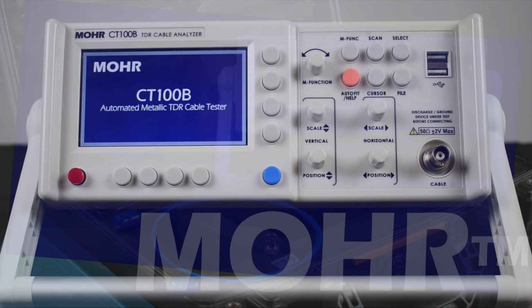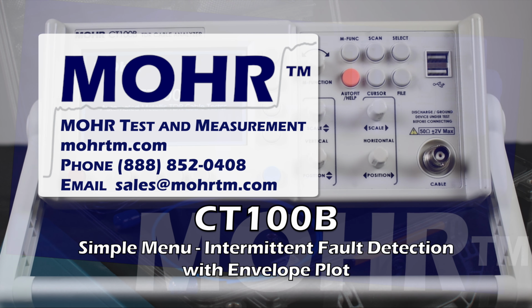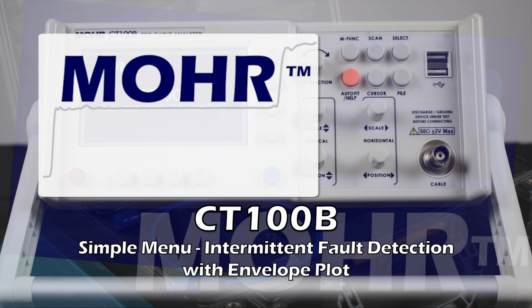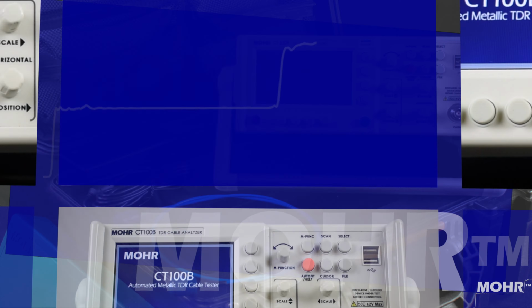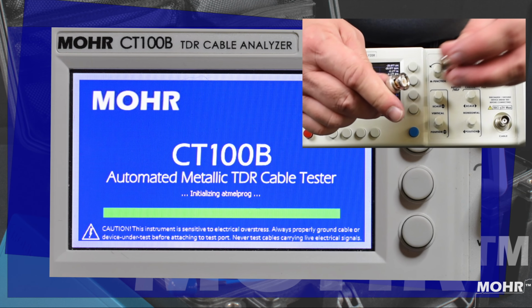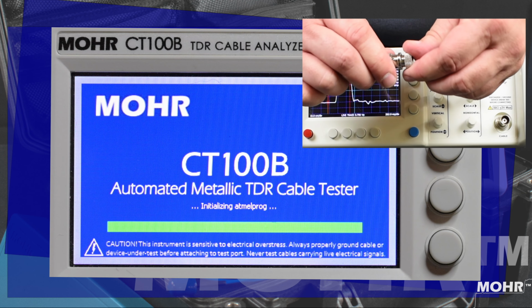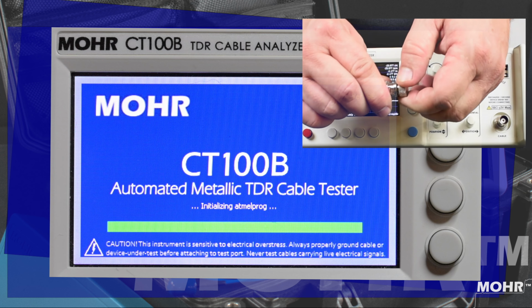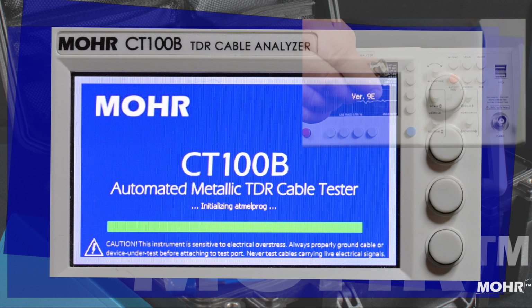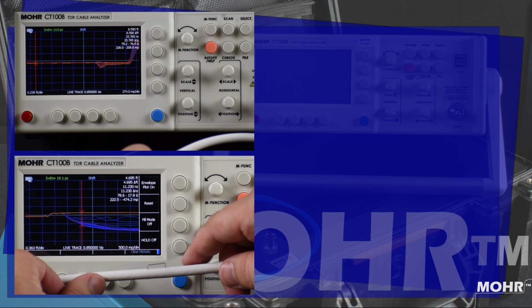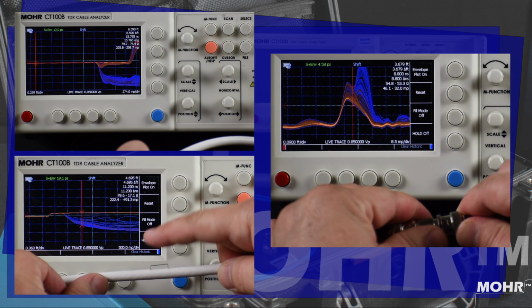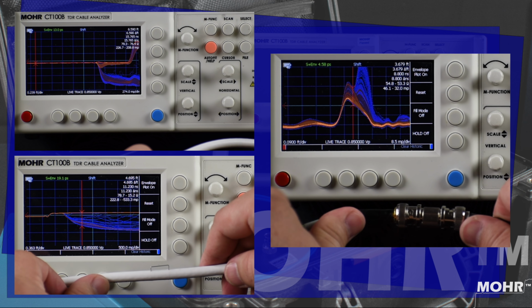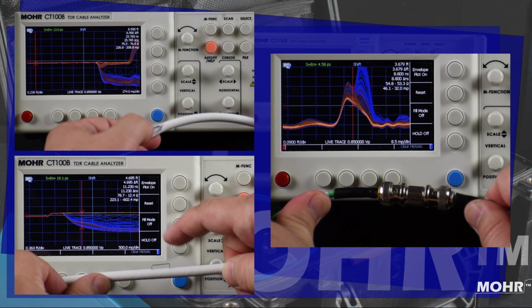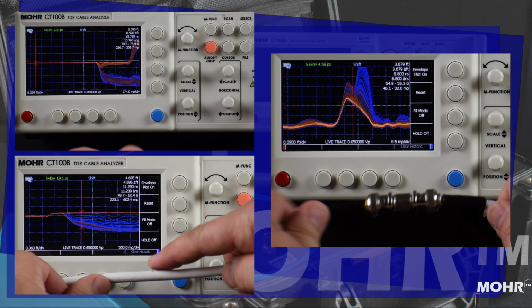Today we're going to use the MOHR CT100B to find intermittent faults with envelope plot in the new simplified menu. Let's get started. Always remember to properly discharge static before connecting to any high-frequency test equipment, and never connect to live equipment. A feature unique to the MOHR CT100 series TDR is the ability to find and locate intermittent transient faults using a function called envelope plot.